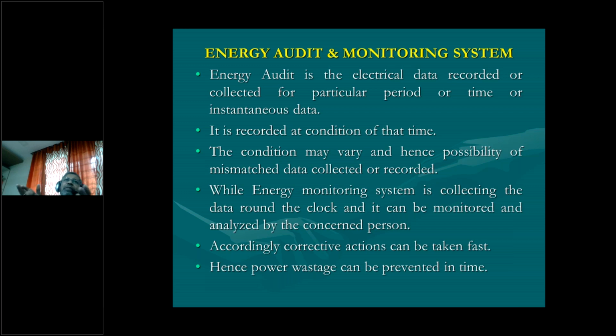See, for energy audit, they may put it for 24 hours or a day or two, but you cannot provide those type of system round the clock or for a long period. So accordingly they work out the data and accordingly they guide us: what are the lacuna, what are the mismatch in the parameters? It is recorded at condition of that time. Now in process or in system, if you're having a different type of production, different type of casting, different type of chemistry in your process industry, if you're doing the audit, suppose your A and B type product were going on, it may not be applicable for C and D also. The condition may vary and hence possibility of mismatched data collected or recorded. Of course, the energy auditor will never misguide you. He says that this is considering your conditions.